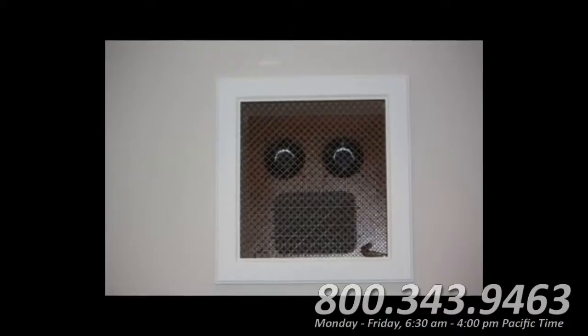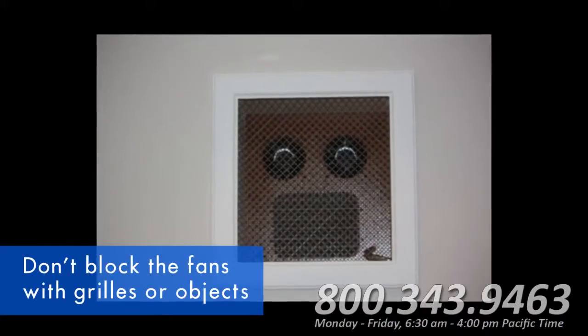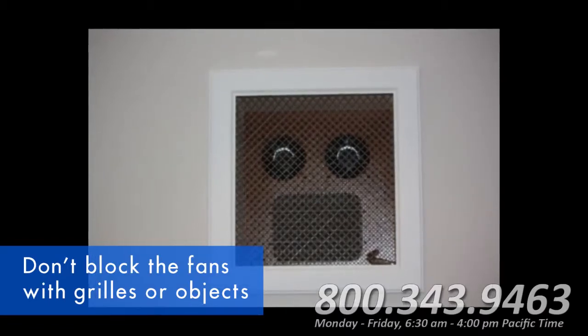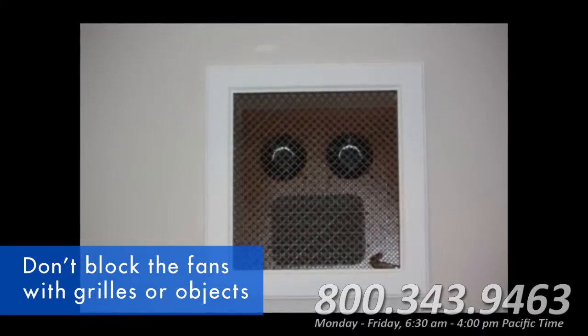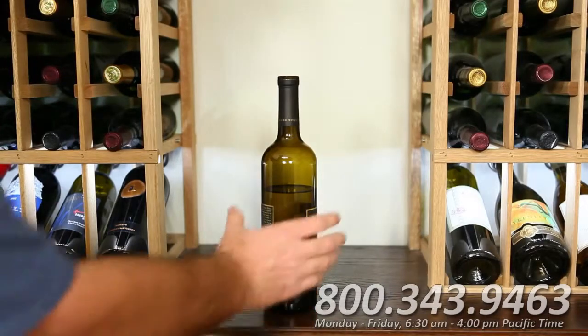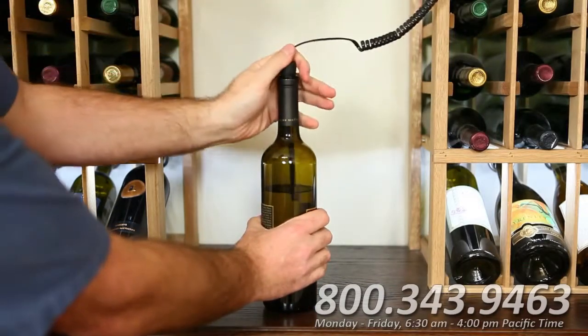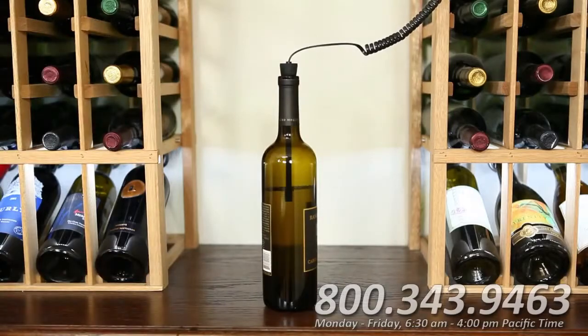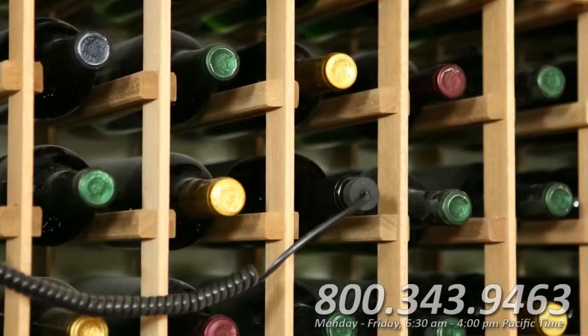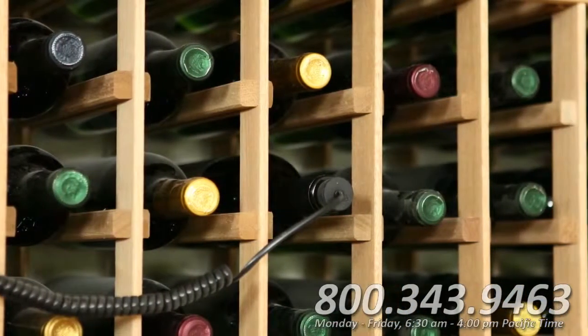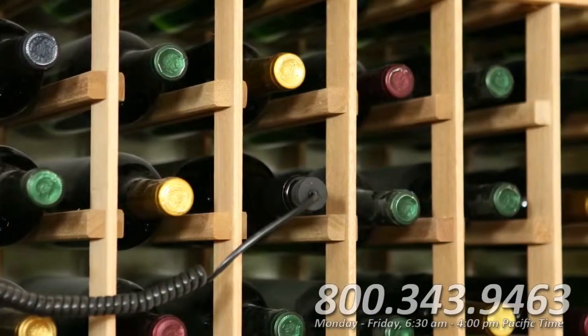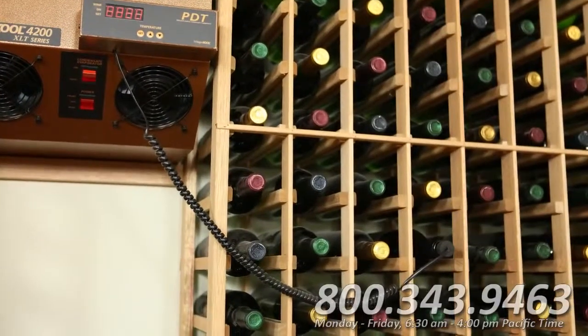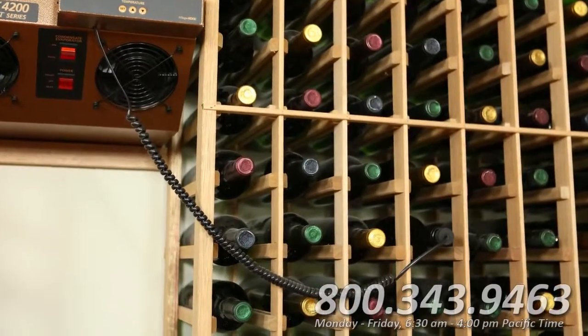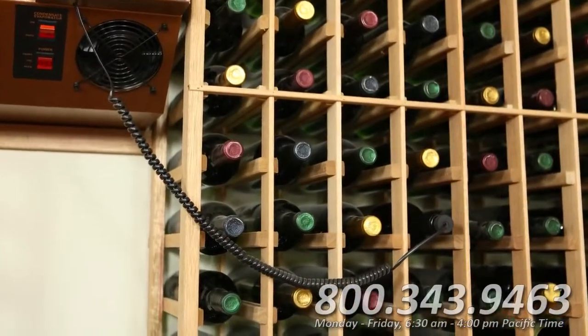Check to see if there is anything blocking the exhaust, as this is the leading cause of icing. If you have attached a decorative grill or placed a plant in front of the exhaust area to hide the unit, you're obstructing the airflow. Don't forget that the liquid temperature probe needs to be securely corked into a wine bottle 3/4 full of regular tap water that is stored in the center of the racking. Reading air temperature instead of liquid temperature can cause the system to run continuously, which leads to icing. The liquid temperature probe should be at least 2 feet away from the unit for proper operation.